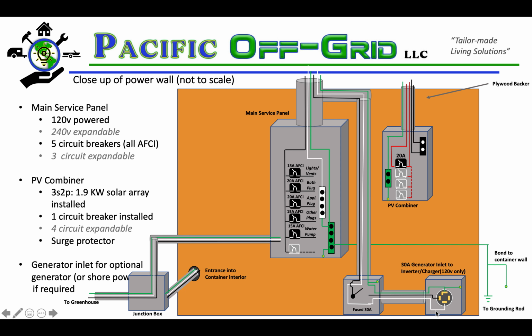However, this design would allow for the client to choose to expand to 240 volt power in the future if future demands dictate a need. In order to ensure the highest levels of safety, we are installing dual function arc fault and ground fault circuit interrupter breakers on every branch circuit, and these breakers offer the highest levels of safety available on the market today.